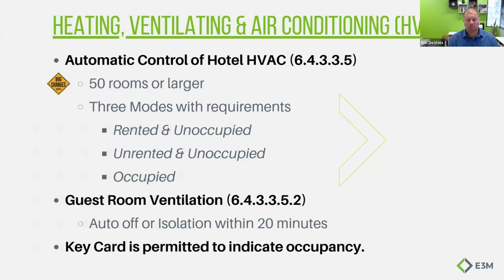What is also really challenging with this is to know that it is unrented and unoccupied. You now essentially have to have an integration between your hotel check-in system and your HVAC controls. You need the front desk to be able to flip something from rented to unrented and back and forth, because that's going to start defining how much your guest room ventilation can run, how much that room is set back or not, if the fan can run. There are different requirements that are all driven by rented or unrented from the front desk, and then occupied or unoccupied within the room.